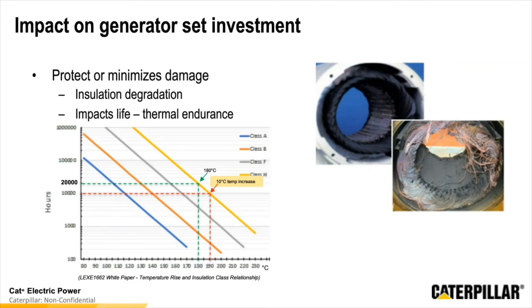So we have a white paper that we'll reference later on the temperature rise and insulation class relationship that walks through the differences that you'll see based on temperature and based on those different classes of insulation. But you also see that in the same classification of insulation, as you increase the temperature by 10 degrees Celsius, you're going to reduce the life of that generator insulation by half. So in this example, a generator with 180 degree C operating temperature, with a Class H insulation, which Caterpillar uses on almost every generator we sell, is going to have about a 20,000 hour life expectancy for that insulation material.